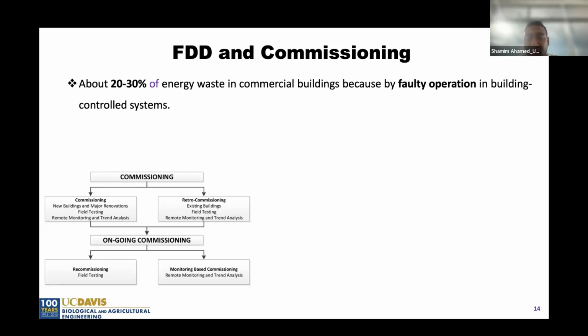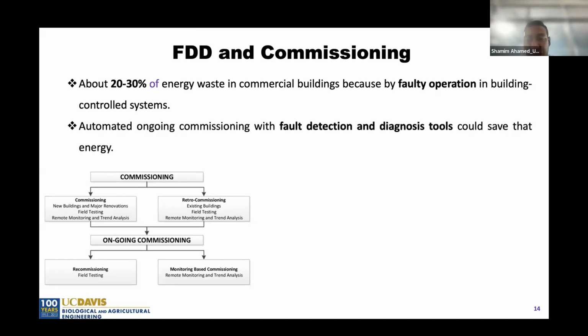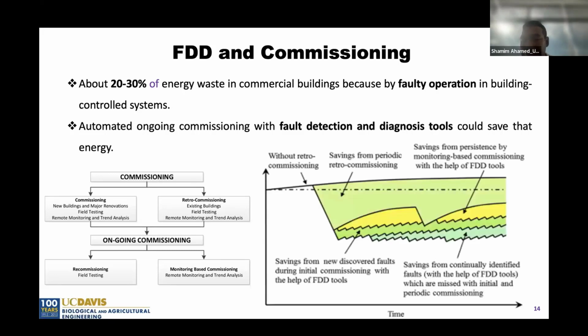In CA, energy is one of the biggest concerns, and faulty data is very common in agricultural applications compared to commercial or residential buildings. So from that perspective, there's huge opportunity to save energy and other resources used in CA facilities. Automatic ongoing commissioning with fault detection and diagnosis could save the energy that's wasted because of wrong information from the sensor.